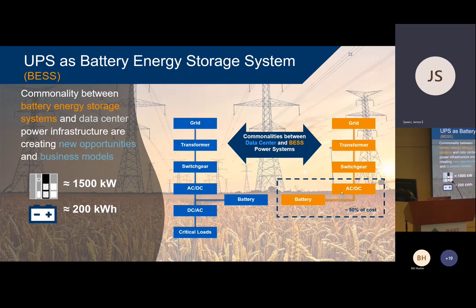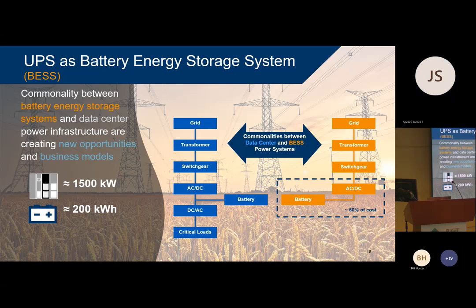So if you already have a UPS and you need an energy storage system, you don't have to start over again with additional new hardware. You could go to your 5-year battery replacement mark and say, okay, maybe I replace my lead battery with lithium. Now I've got a 10-year battery that's rated for lots of charge discharge cycles, and I didn't have to deploy a discrete energy storage system in addition to a UPS system that I already have.